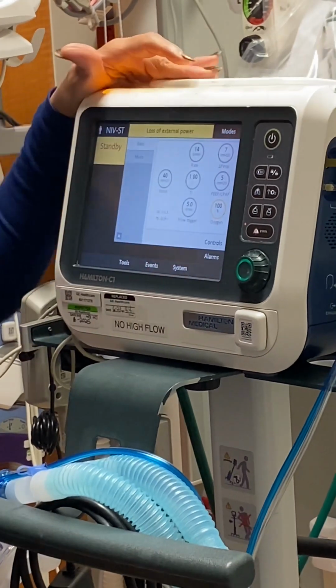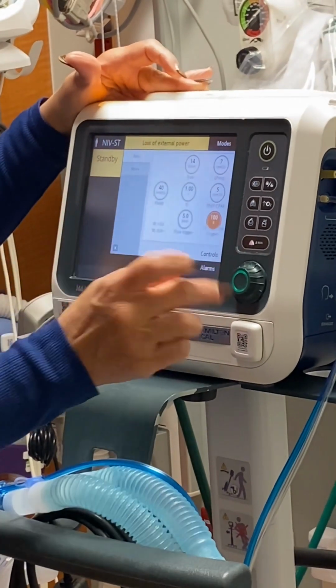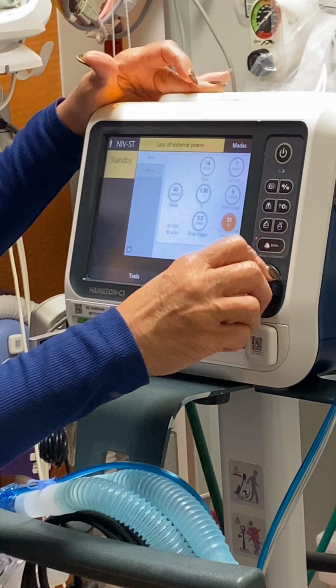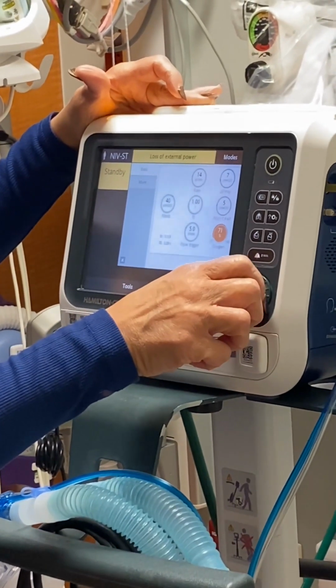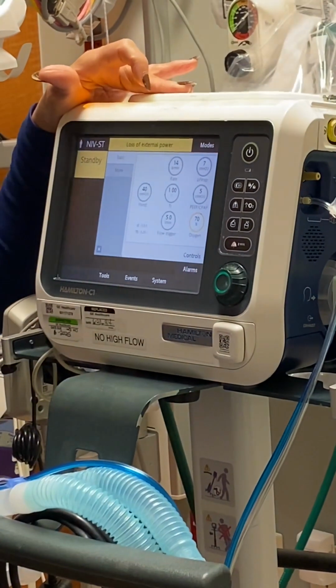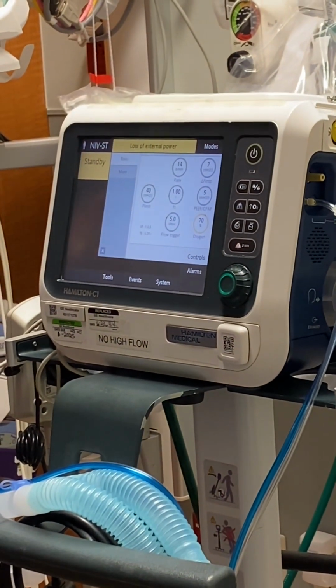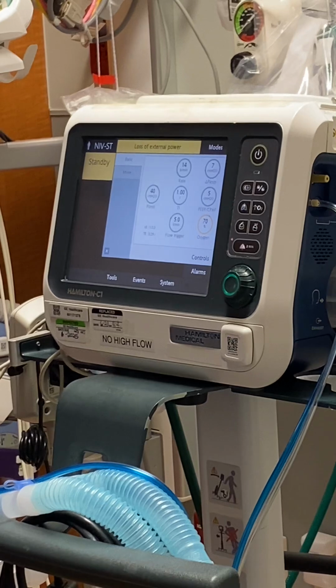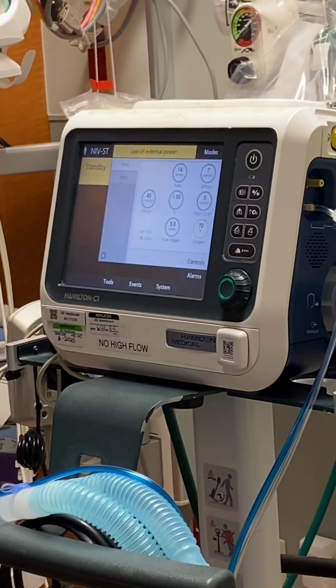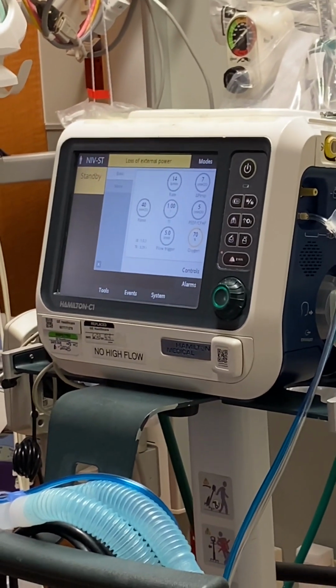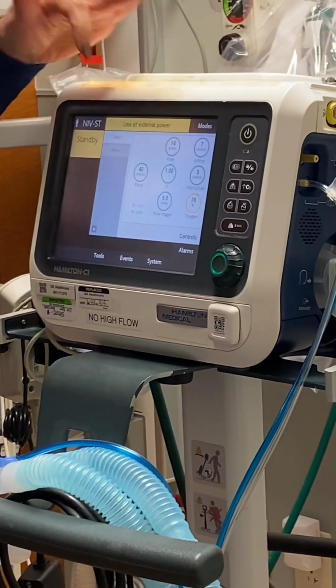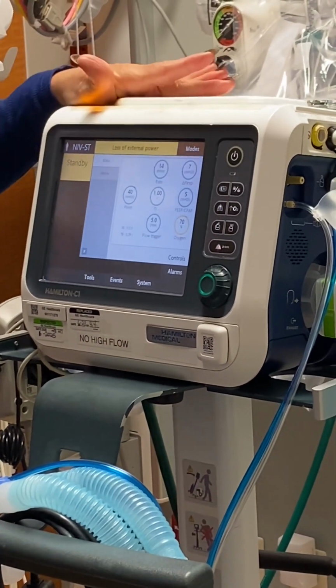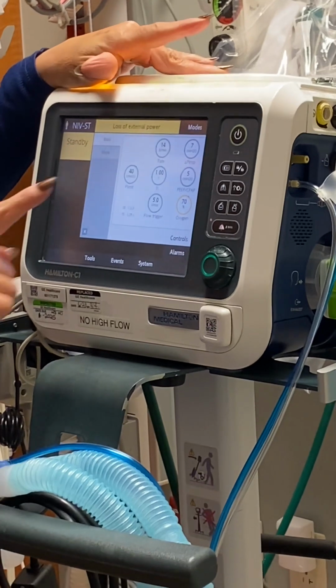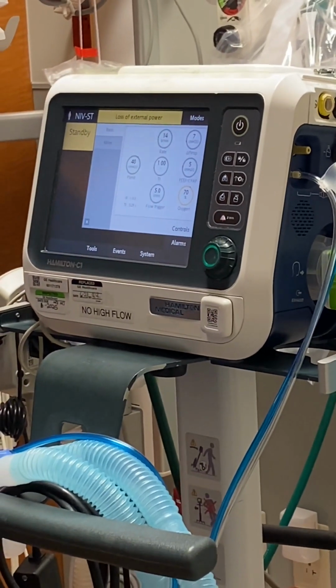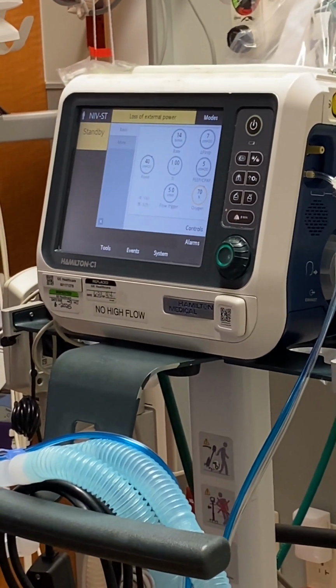You tap it, it goes away. Tap it again, you can change it if they start sounding good. You want to go down, you tap it again, you dial it down. I'm going to go down to 70. You can either press it or tap it. So you can do both. So when you're charting, you would chart 12/5, FiO2 of 70, and backup rate of 14. That would be your charting. Okay? Same thing with here.